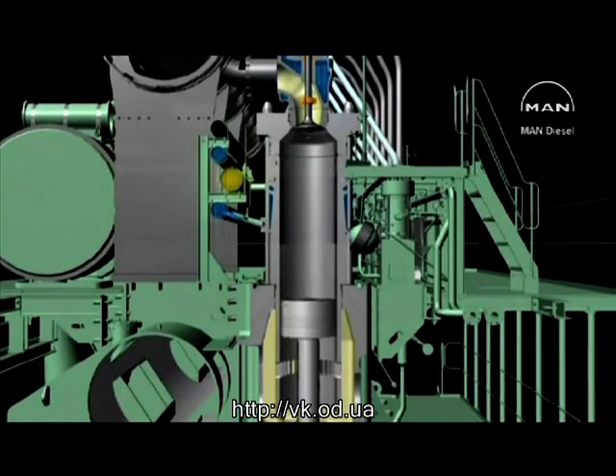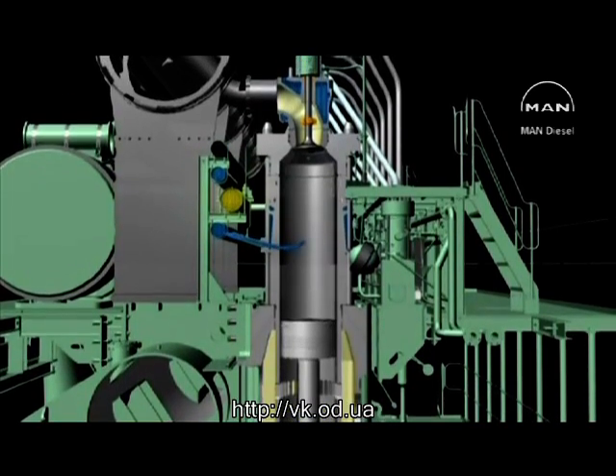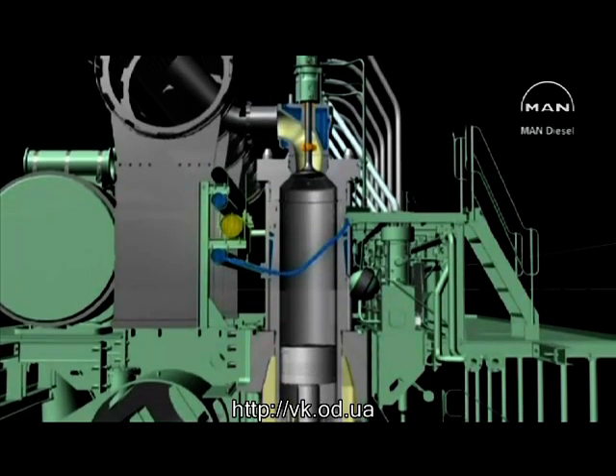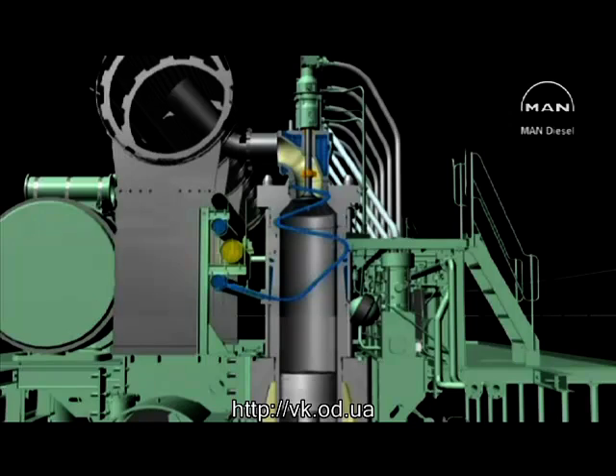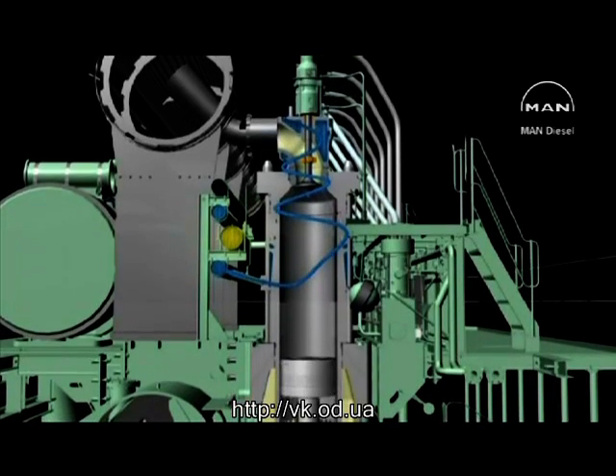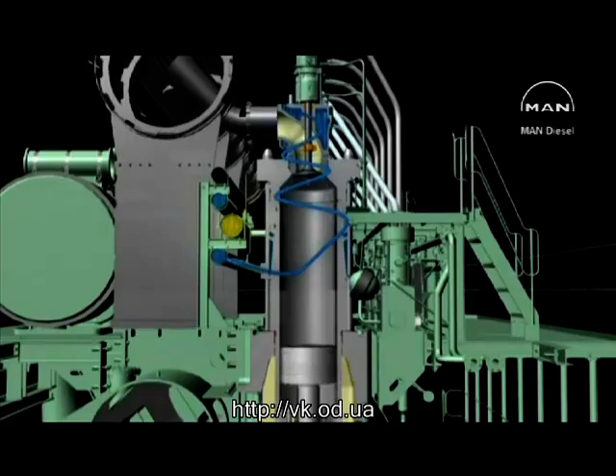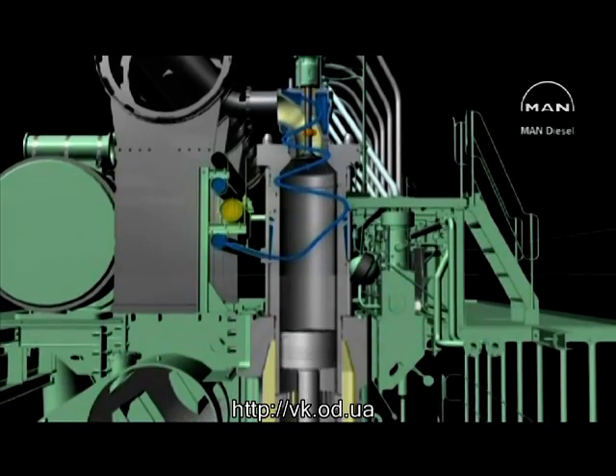It's therefore necessary to provide efficient cooling, partly with oil led through the piston rod up into the piston itself, and partly with water circulating through the cooling jacket around the cylinder and cylinder head, and passing rows of narrow drill channels placed close to the most heavily heat-loaded internal surfaces.